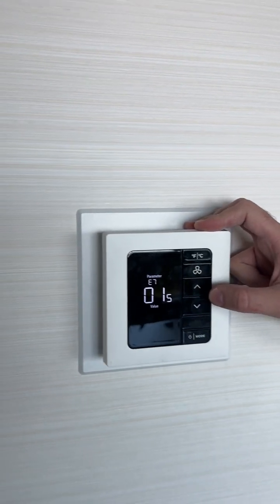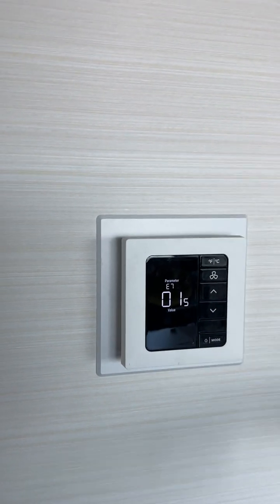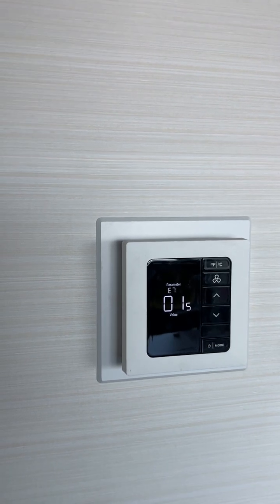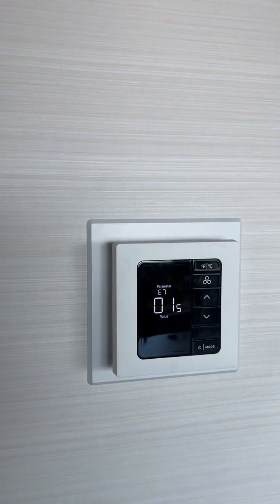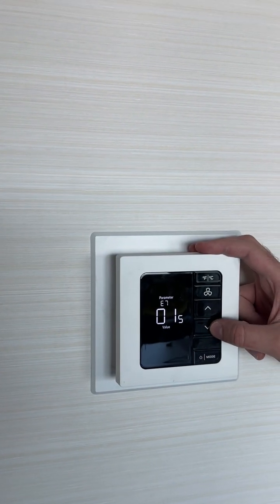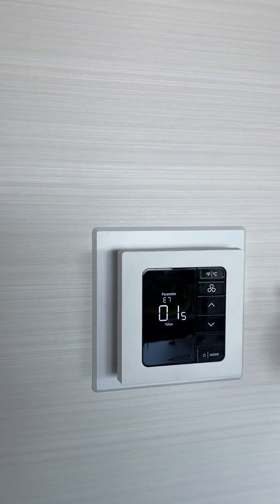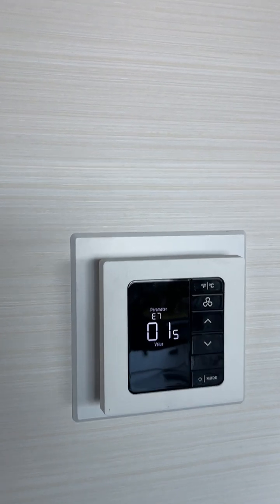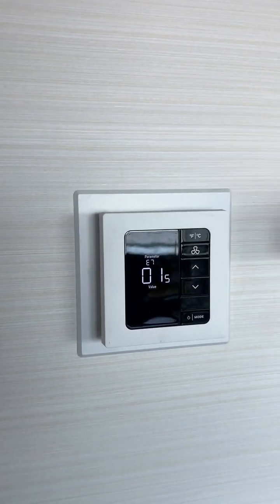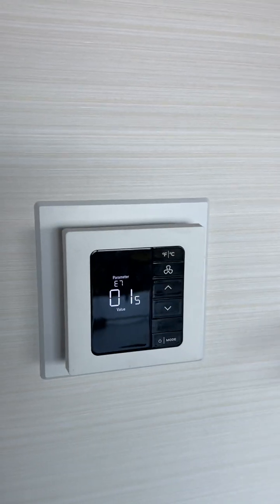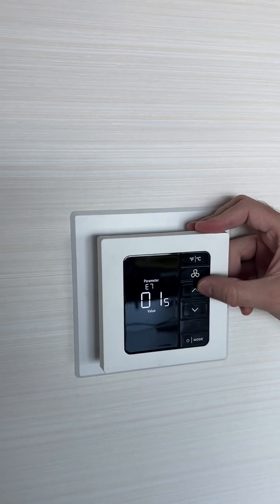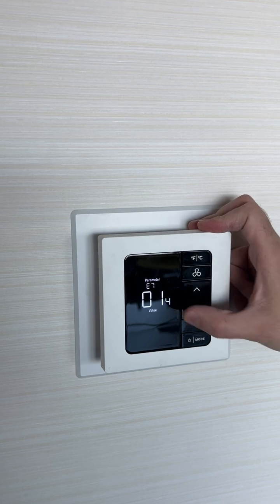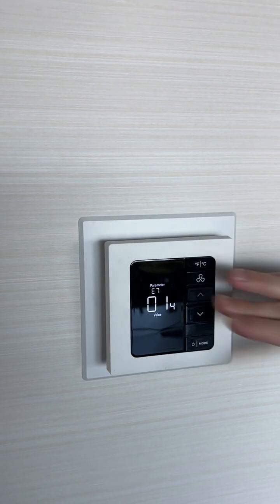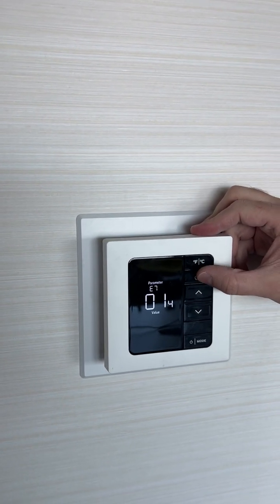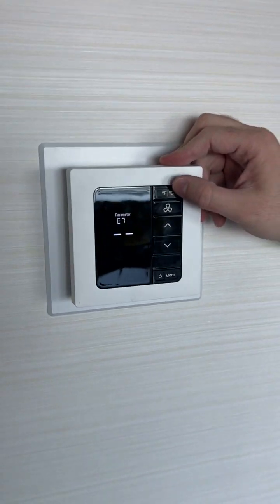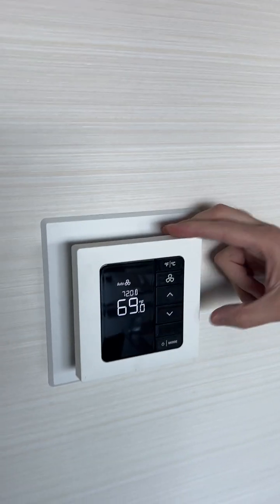So E715 for the secondary thermostat is just saying, hey, you're the secondary thermostat. Don't try to take control of the room. Just listen for messages and act as a kind of bounce point, where if you touch either thermostat, it'll adjust on both. So this is the primary thermostat, this is 14. And fan to save. All right. I'm going to press FC to exit.